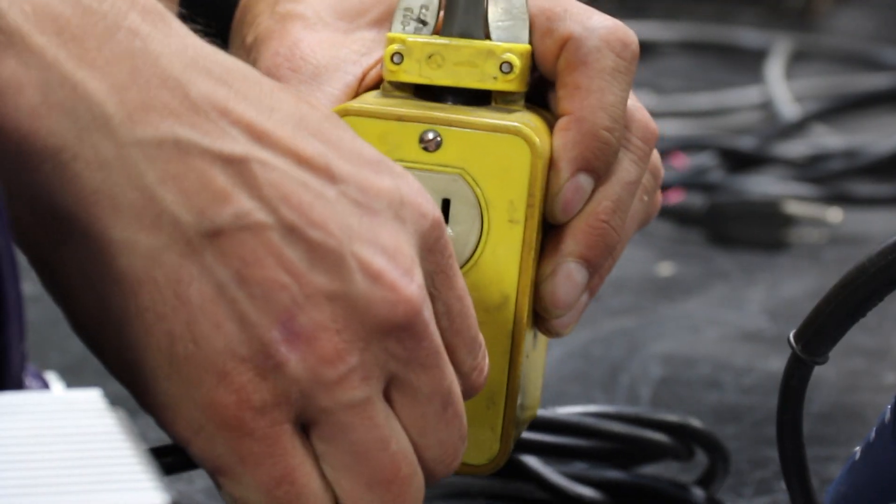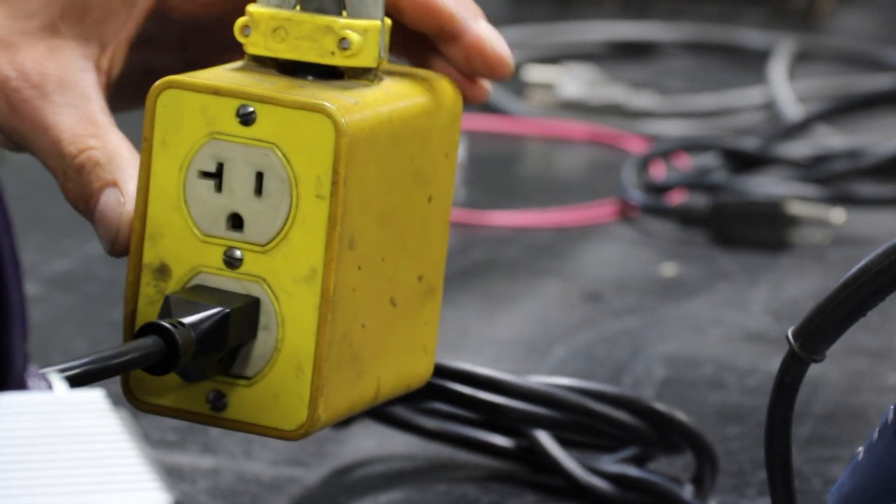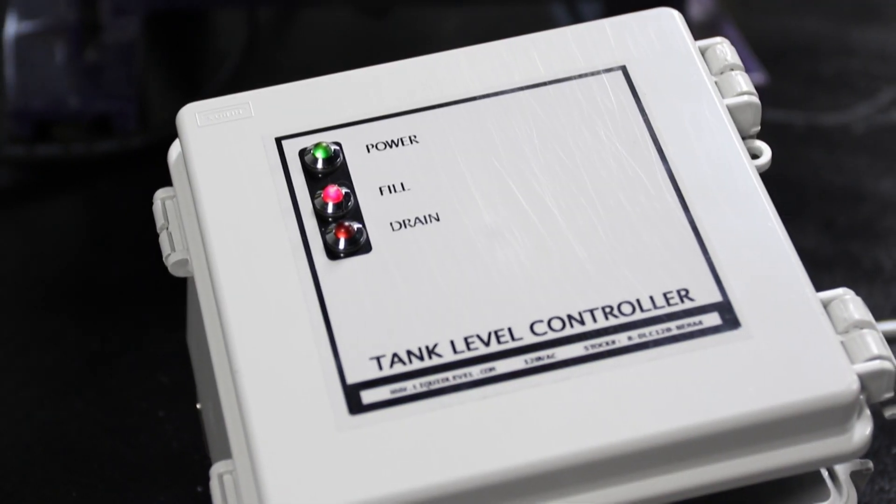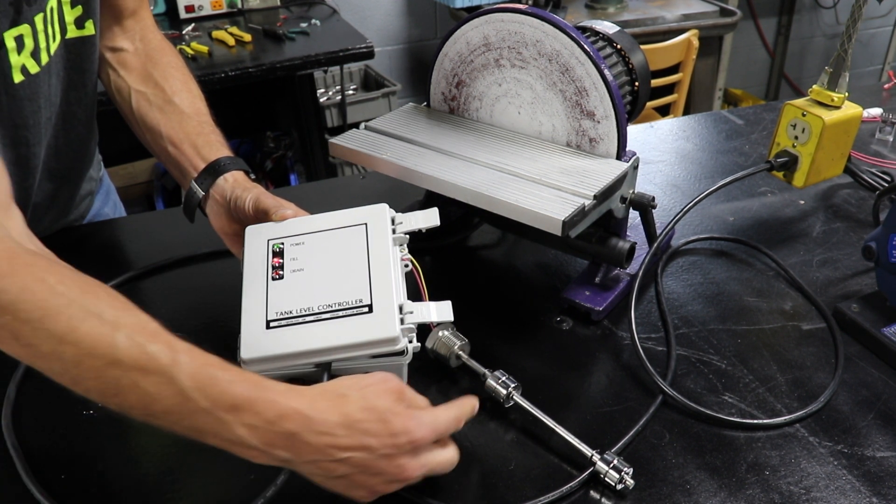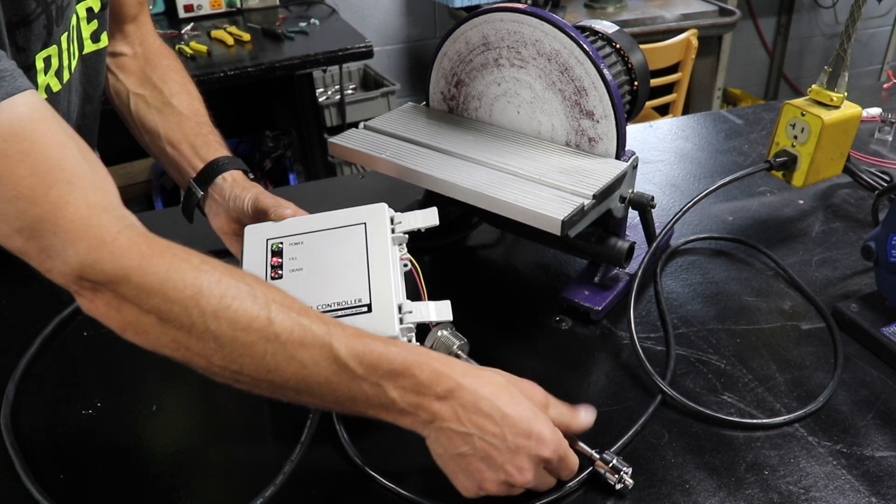Let's plug in the tank level control relay to see how this setup works. Power is indicated by the green LED seen here and the fill light is on because these two floats are in the down position indicating our tank is empty and would begin filling up.